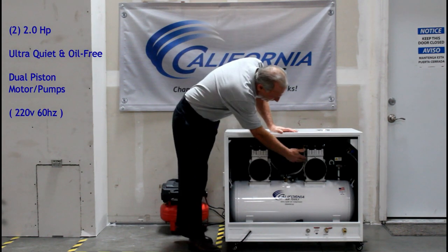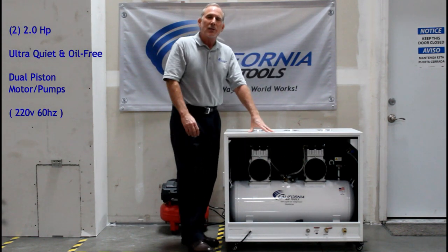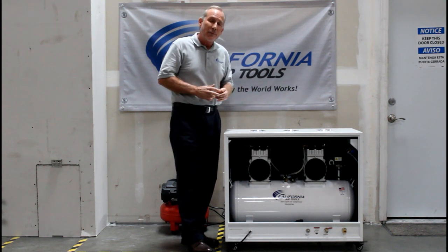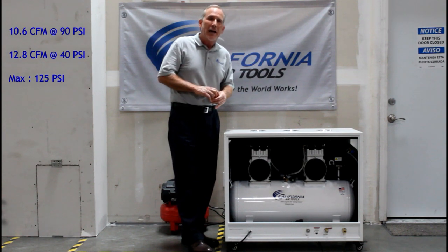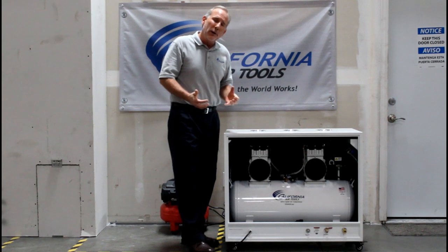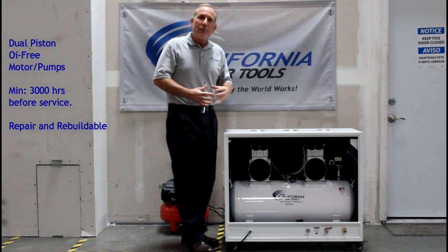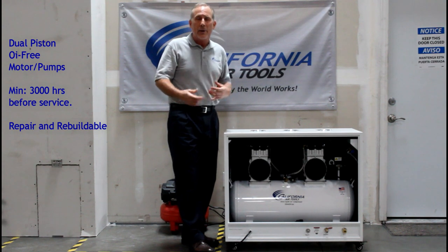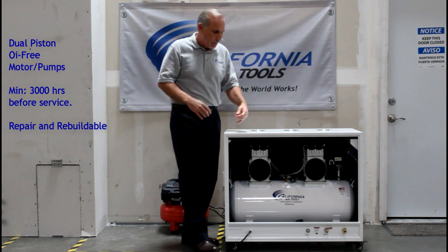Below you'll see we have two 2 horsepower motors. These two 2 horsepower motors work simultaneously to produce 10.6 CFM at 90 PSI and 12.8 CFM at 40 PSI. These are oil-free pumps and motors, and they're designed to last 3,000 hours before service or wear, and they're easily serviced and repairable.